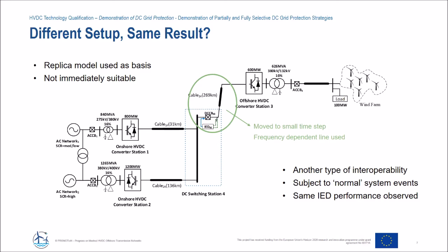It also meant that we could subject the IEDs to normal system activities. When using the replicas, part of the reason we could use this for extensive testing is that we had to run through the normal startup and shutdown sequence using the replica interface. This meant we subjected the IEDs to a full startup sequence, and they rode through them without doing any spurious trips. So that's further confirmation of the viability of these protection system schemes.